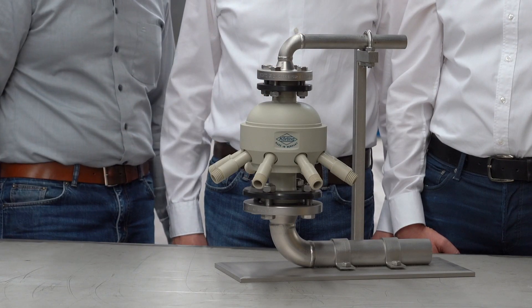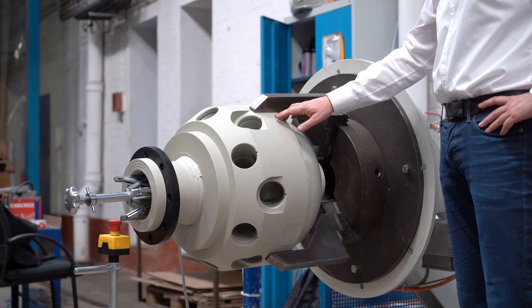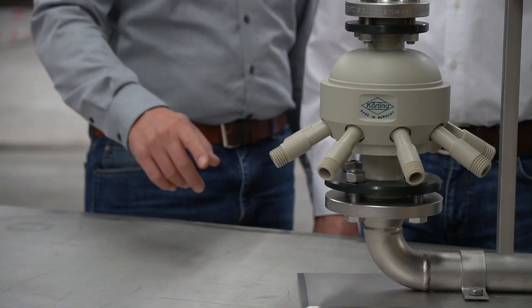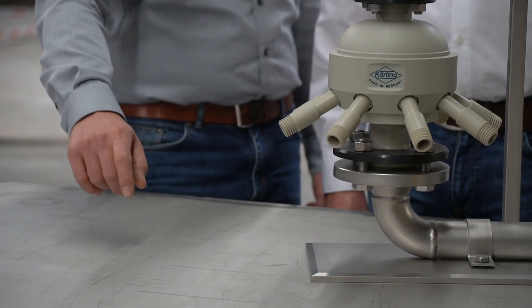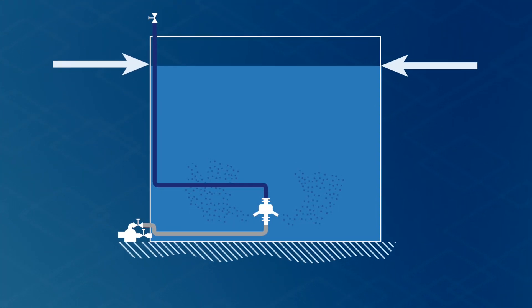Each ejector is detachable from the manifold casing and supplied with wastewater from the bottom and compressed air from the top. Two flanges on the wastewater and compressed air side make the ejector easy to fit. The tank shape defines the necessary number of multipass ejectors. All ejectors are connected together via a pipeline system. The jet stream pointing downwards prevents deposits and also allows usage of the full water depth for oxygen transfer.